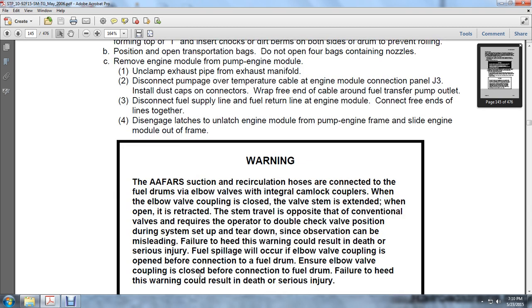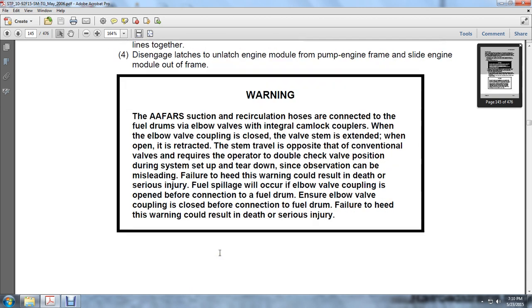Warning. The Advanced Aviation Forward Area Refueling System suction recirculation hoses are connected to the fuel drum via elbow valves with unisex cam lock couplers. When the elbow valve is closed, the valve stem is extended. When the valve is open, the stem is retracted, opposite of conventional valves. This requires the operator to double check the valve positions during system setup and teardown, since observations can be misleading. Failure to heed this warning could result in death or serious injury. Fuel spillage will occur if an elbow coupling is open before connection to the fuel drum. Ensure the elbow valve coupling is closed before connection to the fuel drum. Failure to heed the warning can result in death or serious injury.